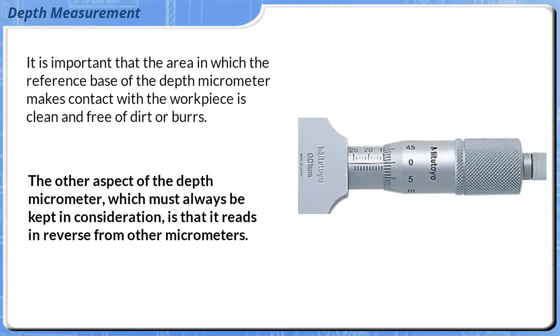The other aspect of the depth micrometer, which must always be kept in consideration, is that it reads in reverse from other micrometers.